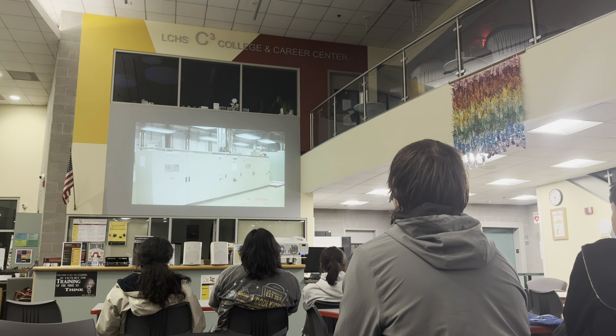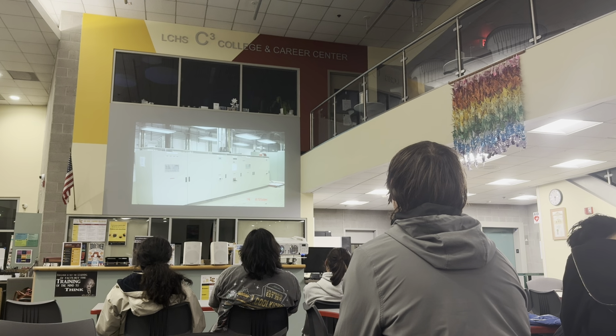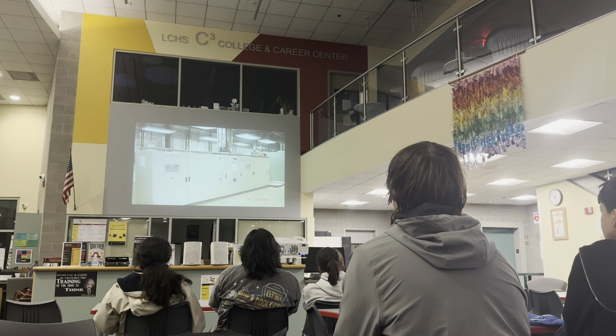This is a UPS. You have to know which loads require power. If power goes out, if there's an emergency and you don't have power, which devices should be operating in order to bring down the facility safely and shut it down. So all that equipment, switches, or transmitters, they all go on the UPS system. So you size the UPS, there's a calculation for that. This is what a UPS looks like.